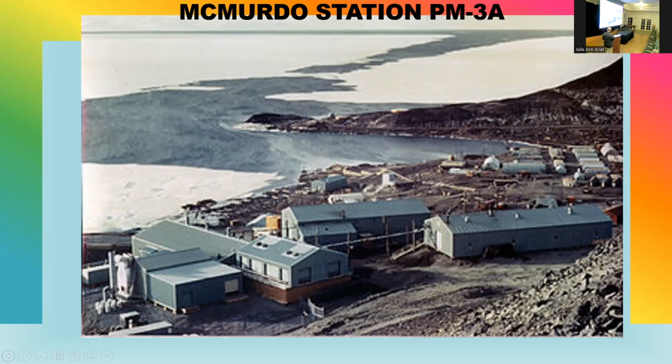Down the end of that building, this was my office in this corner, and we had a lounge, health physics laboratory. This was our air-cooled condenser, if you will. You'll notice these large doors on the side. These doors would roll up a little bit as far as you wanted them. And in the ceiling, in the roof, were 8 fans. With the air coming in underneath the doors, running across tubes of a condenser, and then exiting through the ceiling, through the roof, being drawn by those fans was the cooling operation that we had. The low pressure steam from the turbine entered the tubes as low pressure steam. It exited as water. And occasionally, when the control room operator wasn't paying attention, it tried to exit as ice cubes, and the tube would freeze up, and that was a maintenance problem.